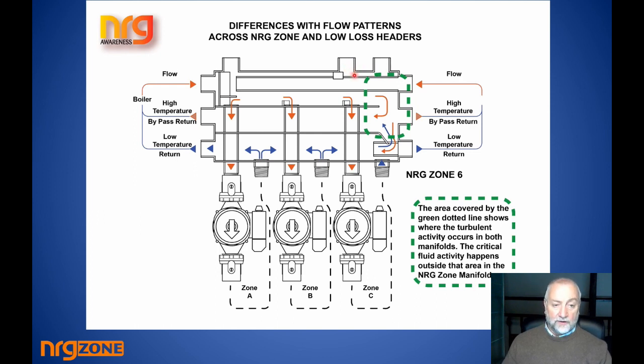And again, that's another governing factor with regard to neutral point. If you have a neutral point in the system, it's where all of those combined zones are commoned into this chamber, and that chamber is open to neutral point, and all of the returns coming back are collected in this lower return chamber, and they're connected to neutral point. So therefore you can categorically say that this area here is the neutral point of the system, and that's where expansion should be taken in, where cold feed should be taken in, and where all the neutralizing effects of all the positive effects that are required for a proper system are located.